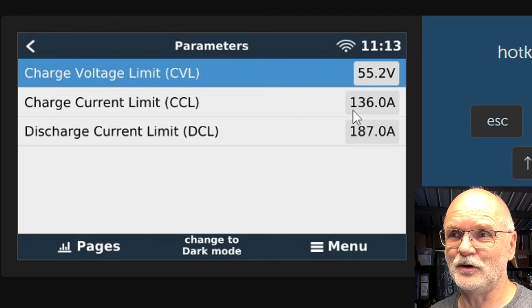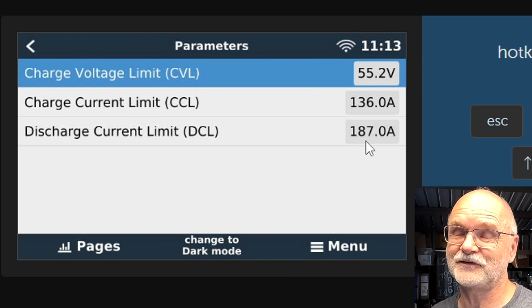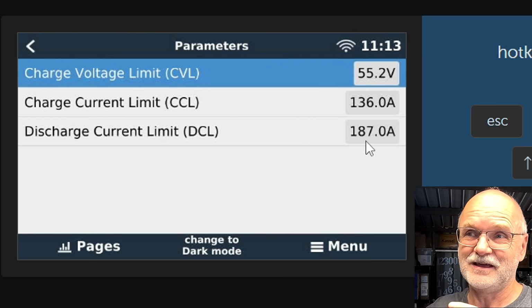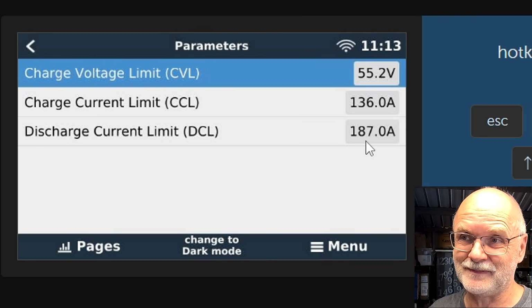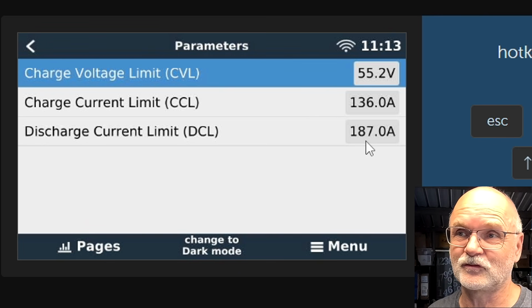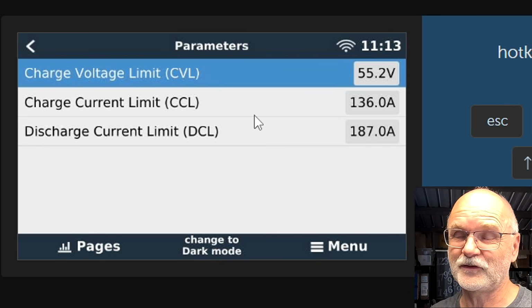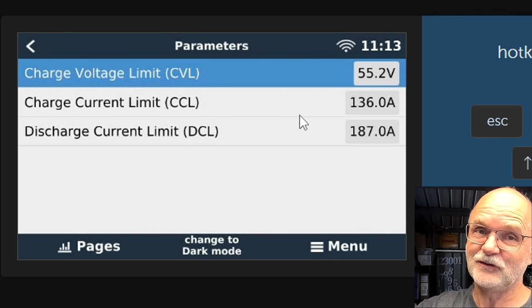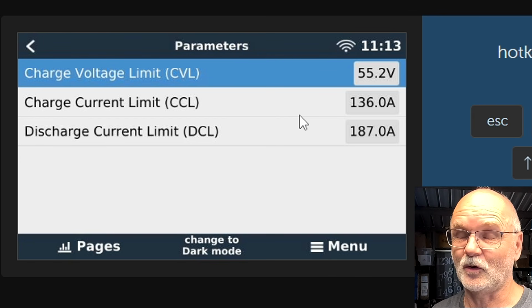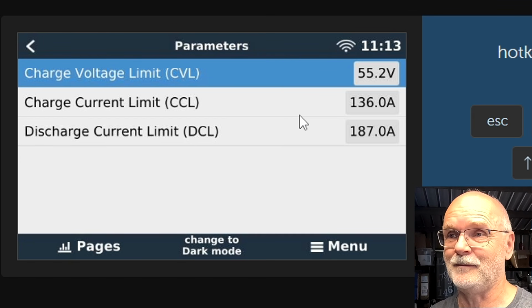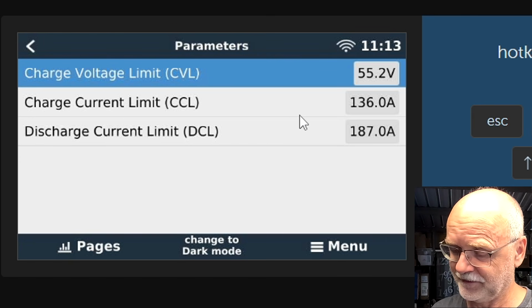And these 136 amps charge and 187 amps discharge current is an aggregated data value from all 3 BMSs, which the master does and reports this to the Victron system here. So at the moment, all 3 BMSs would take 136 amps maximum, and then Venus OS would throttle down your inverter or your MPPTs. So we would not exceed 136 amps at the moment, which is good.